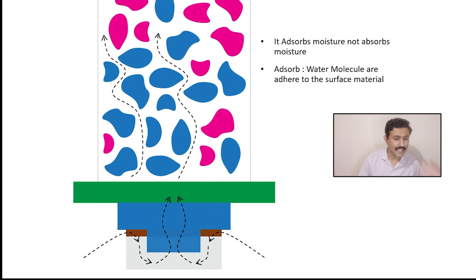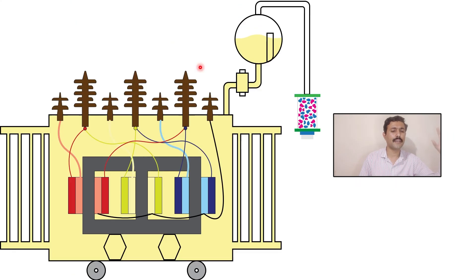Let me show you - this is a silica gel and you can see it is a porous material. There are small holes into a silica gel piece. When air flows through this porous material, the water particles get adhered in these porous holes and it will remove moisture from the air. When this silica gel keeps on adsorbing moisture from the air, it will slowly turn from blue to pink. When it turns fully pink, it is saturated and can no more further adsorb any moisture. This air keeps on moving in upper direction and enters into the conservator tank.